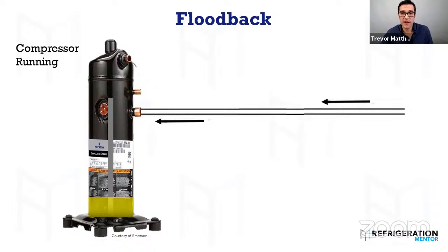Because if you're flooding the evaporator, each evaporator has a specific superheat at which it works the most efficiently and effectively. So you need to talk to that evaporator manufacturer and find out, should I be doing it at 8 degrees Fahrenheit, 5 degrees Fahrenheit, 10 degrees Fahrenheit, 2K, 4K, 6K, depending on the manufacturer. They'll tell you what the most optimal superheat is for that evaporator. If you reduce the superheat, you're just putting a Band-Aid on the system. There's a design flaw there if the suction line was too big and you don't have that velocity coming back to cool the compressor.